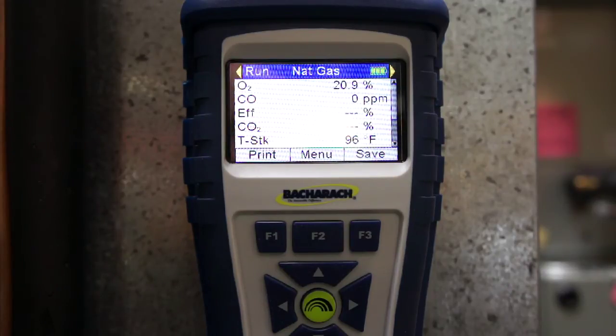And so you get an idea about the CO response time, or the instrument response time here. It does have a fairly long hose, so it does take a second, but once the gas gets into the sensors, it goes very, very quickly. Some of the lines down at the bottom, you'll see they were dashed for a minute, and that's simply because those are calculations, and until the O2 gets down below 16% or so, it's not going to start to make any calculation at all. And you can see there we had a nice high peak CO reading.